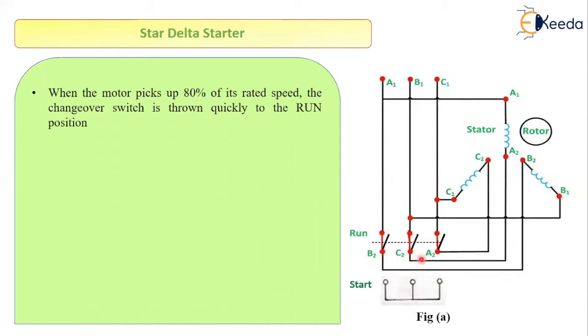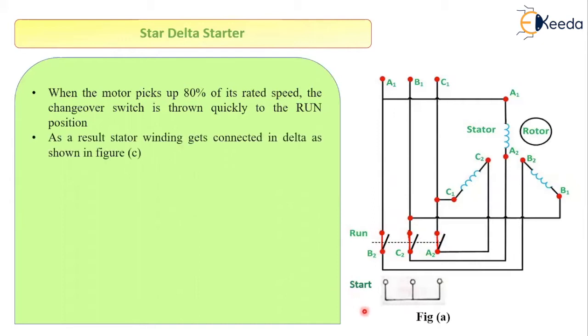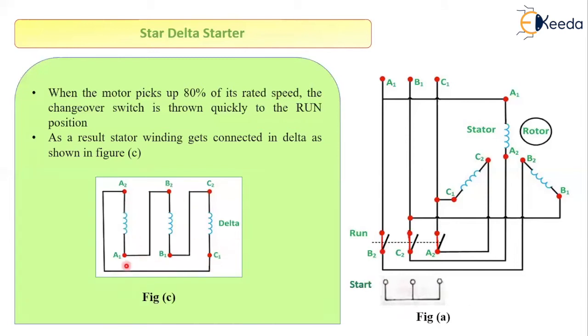Once the changeover switch is thrown at the run position, the B2 terminal is connected to run position, C2 is connected to run position, and A2 is also connected to run position. In this case, the stator of the induction motor will get connected in delta, just as shown in figure C. You can see where A2, C2, and B2 terminals are connected. So initially the motor was connected in star, and once it picked up 80% of its rated speed it got connected in delta.